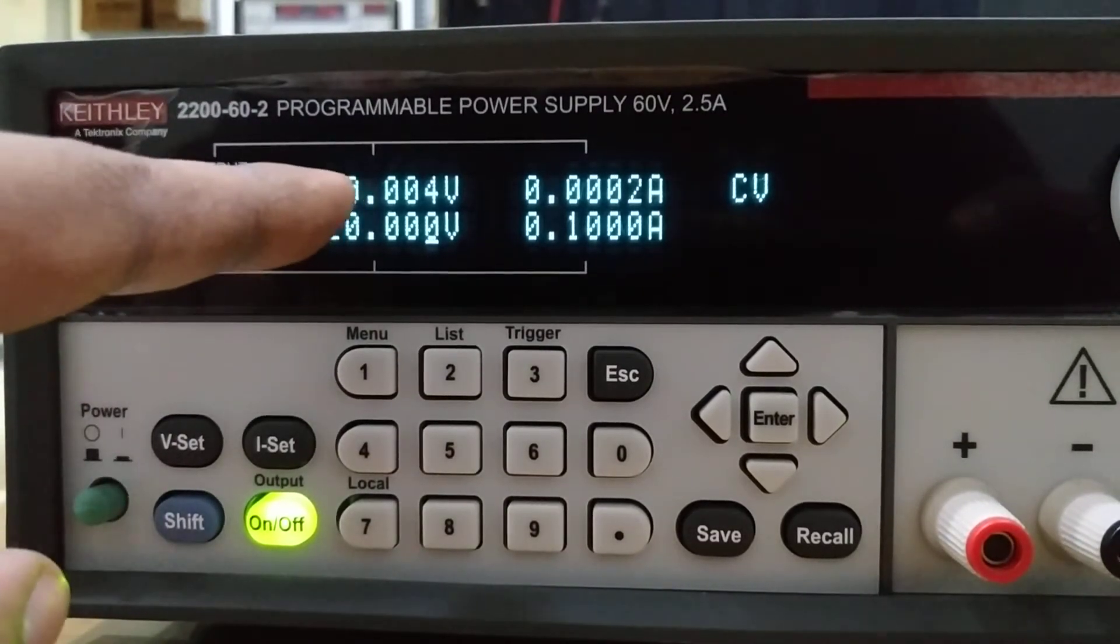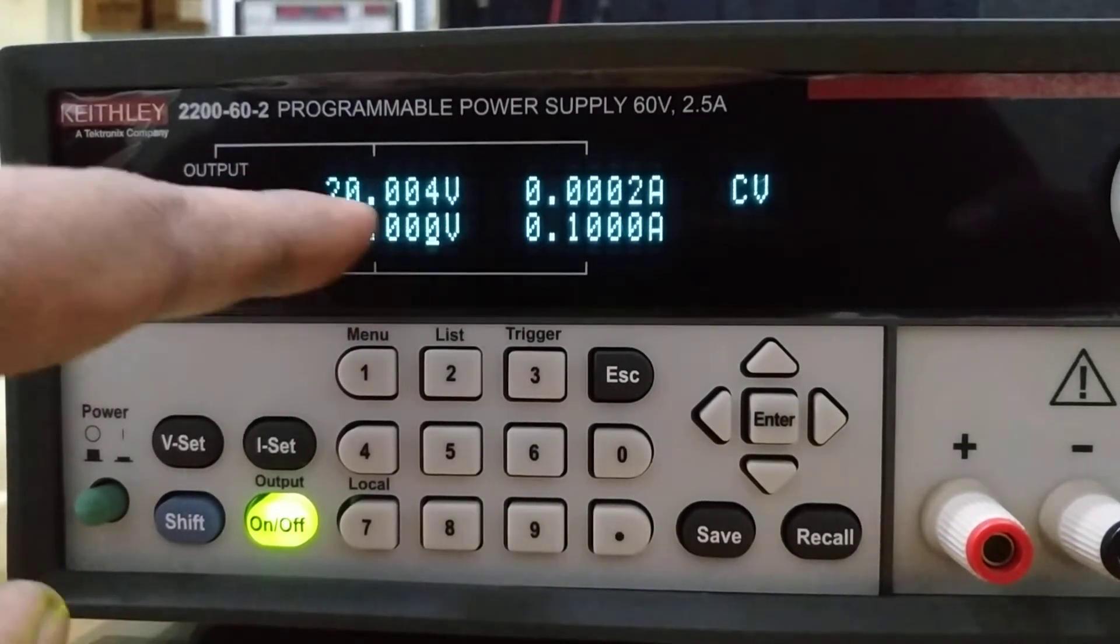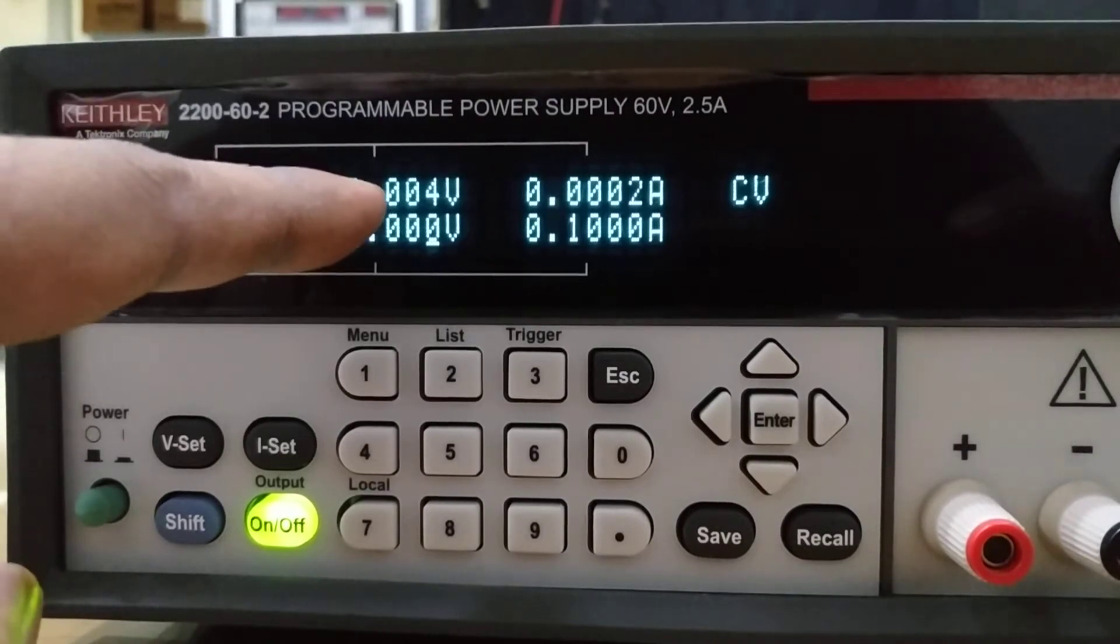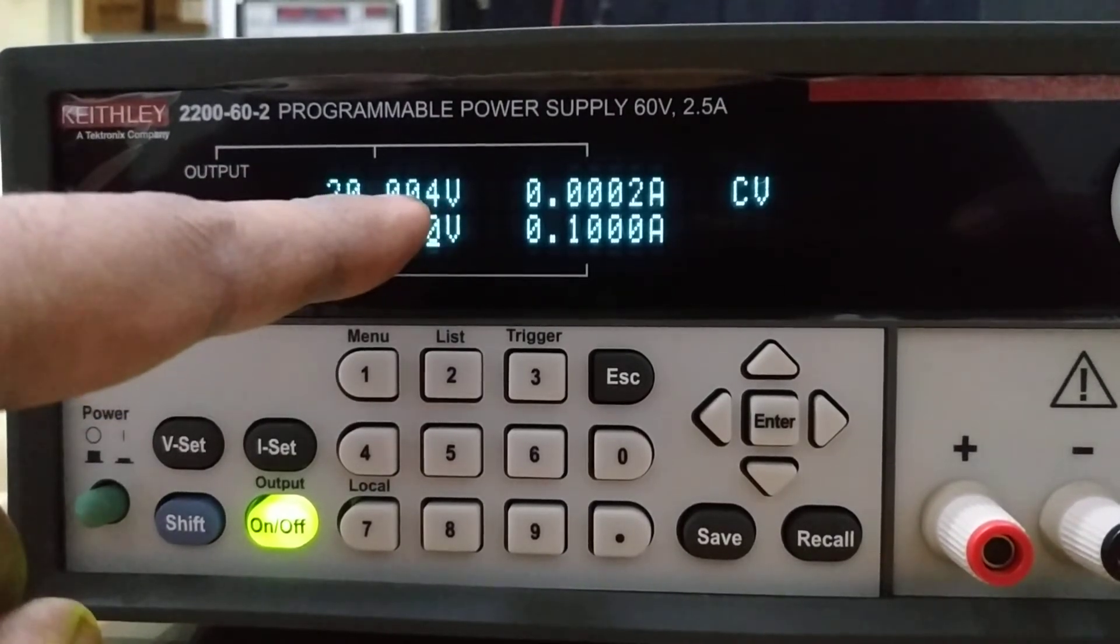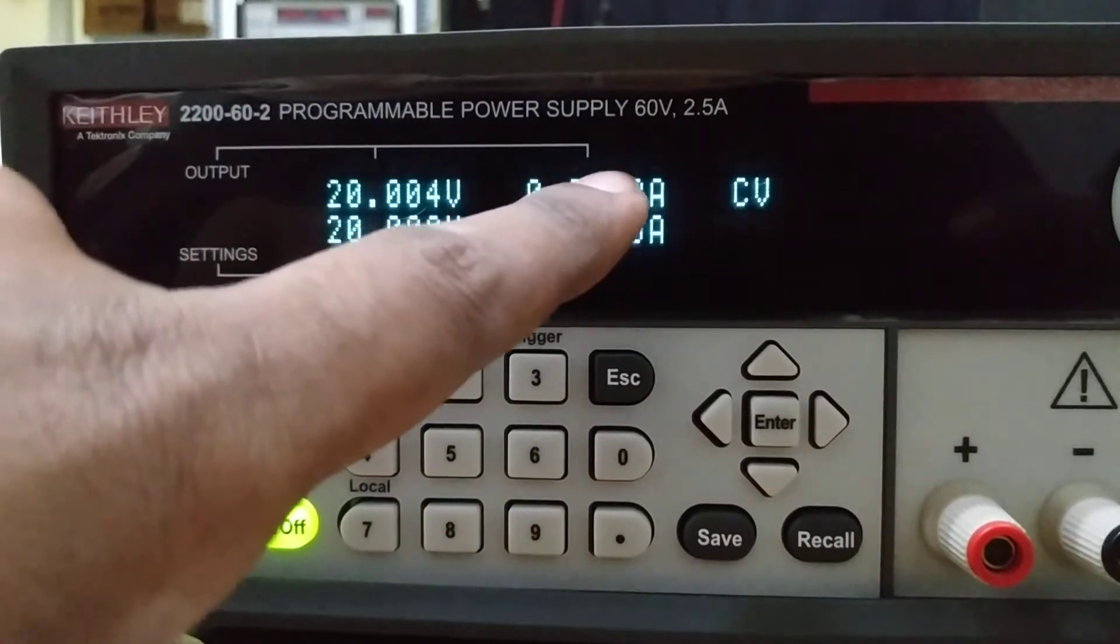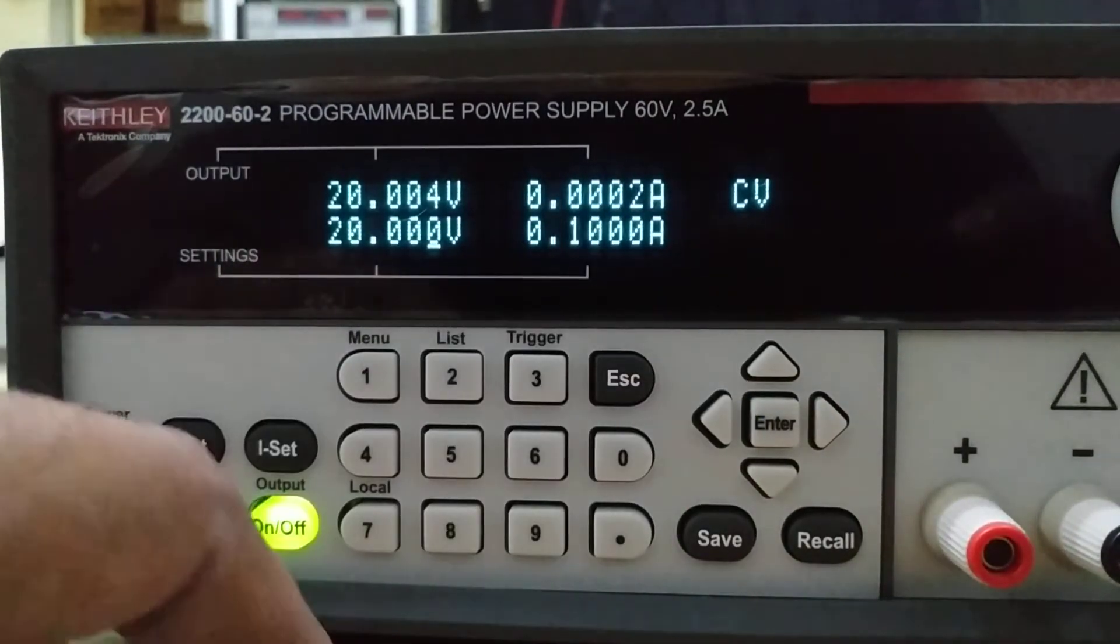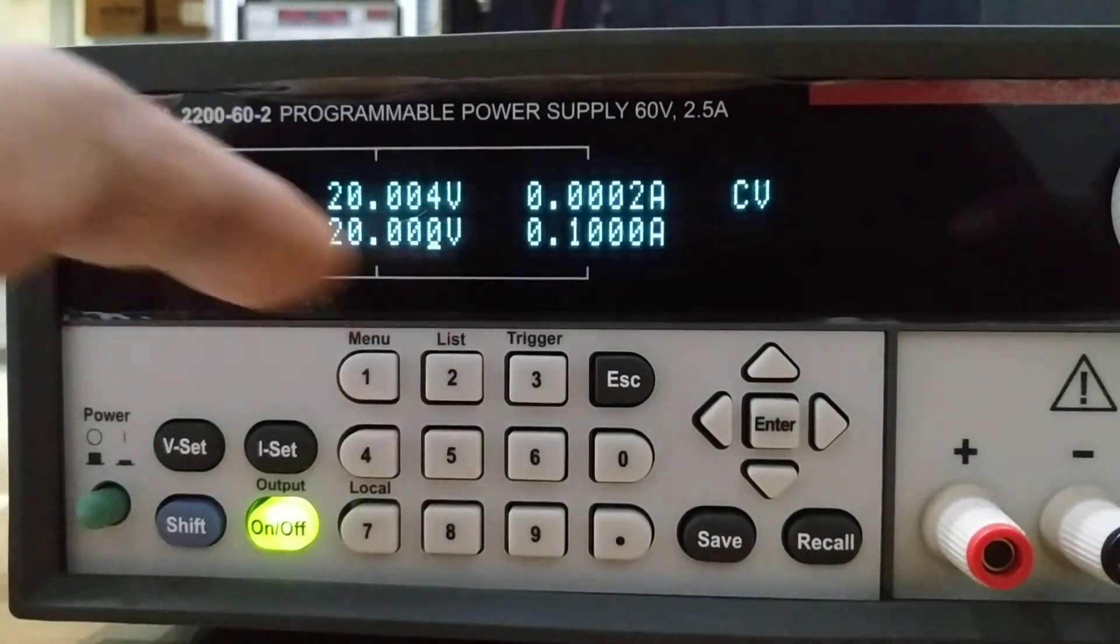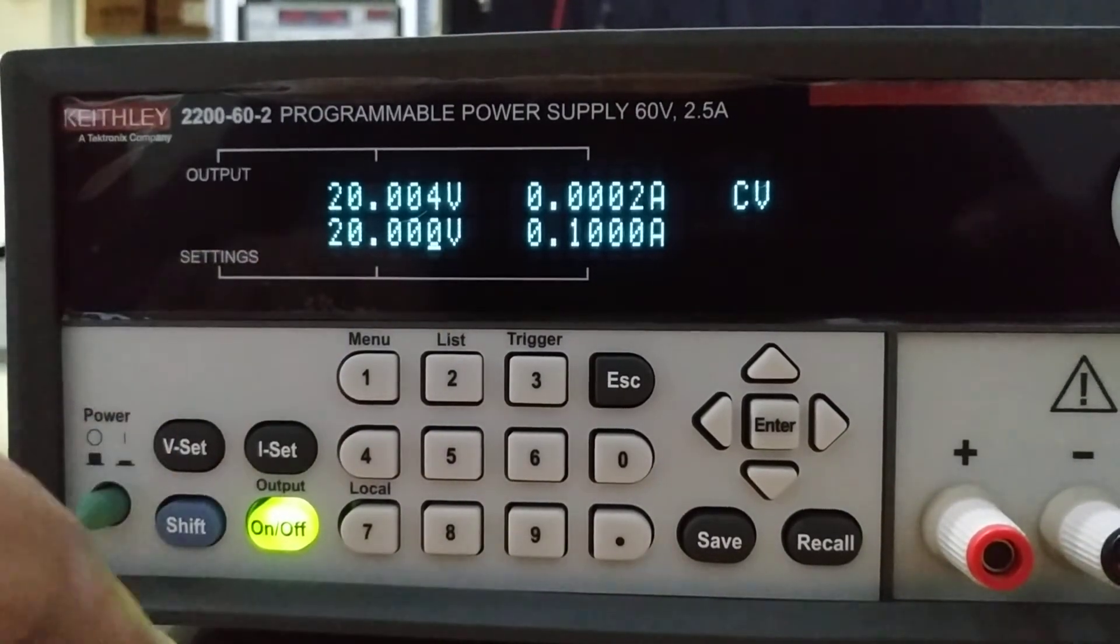Now turn the output on. It's very simple. You can see the output voltage you set is 20 volts and what it's applying is 20.004 volts. The current it's applying is 0.0002 amperes. This is how you can use the instrument in constant voltage mode.